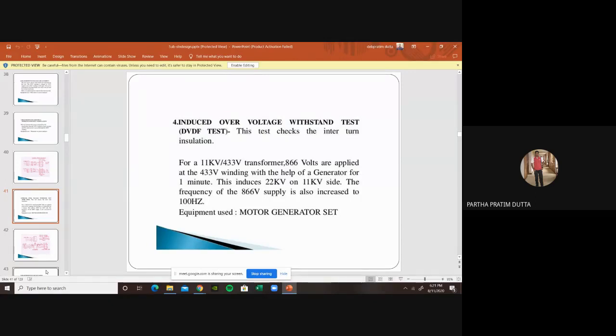Why? As we know from basic electrical theory, the V by F ratio should always be constant in a transformer. So when we double the voltage, the frequency should be doubled. Through the machine, the frequency can be doubled in two ways, either by changing the speed or by changing the pole. So we double the pole numbers in that machine. There is a possibility to set the pole number, and by doubling it we create the double frequency for the voltage being fed to the transformer. Thus we can understand whether this transformer is able to withstand, in the core and the inter-turn insulation, double voltage and double frequency.